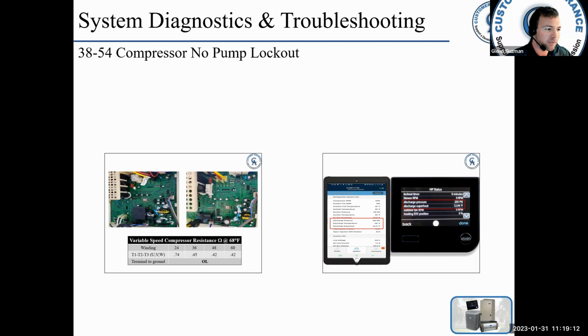What's that? 3854. The diagnostic checks ensure the compressor is running in the correct direction and pumping properly. Once the compressor speed is greater than 400 RPM, the compressor has up to 30 seconds to increase the pressure differential between the discharge and suction by 20 PSI. Okay, if the pressure differential is not met, then you get the code 3854.